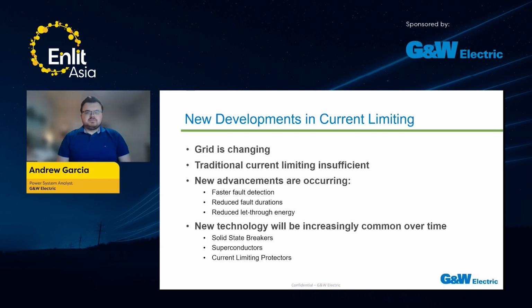So, all about those new developments in current limiting. Once again, just to reiterate what Jimmy said before, the grid is changing in a lot of ways. It's changing in ways that make traditional current limiting insufficient for the needs of the grid today. As a result, there's a high demand for different technology, and new advancements are occurring as a result. And these advancements promise faster fault detection, reduced fault durations, and ultimately, the most important part, the reduced let-through energy. And we anticipate that these new technologies are going to be increasingly common over time.